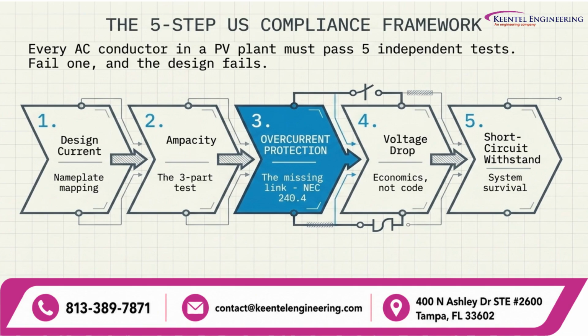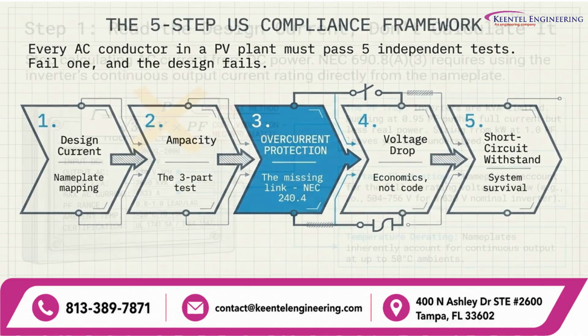Step 1 is mapping your design current directly from inverter nameplates. Step 2 is the NEC ampacity test. Step 3 is overcurrent protection compliance under Article 240.4. Step 4 evaluates voltage drop from an economic and operational standpoint. Finally, Step 5 verifies short-circuit withstand capabilities, so conductors survive major fault events.